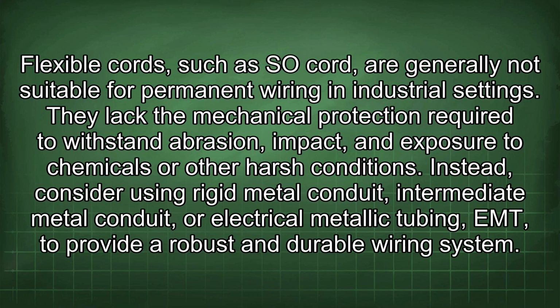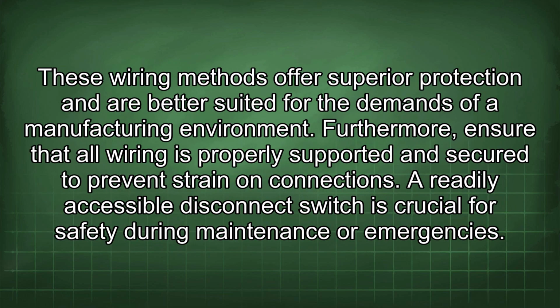Flexible cords, such as SO cord, are generally not suitable for permanent wiring in industrial settings. They lack the mechanical protection required to withstand abrasion, impact, and exposure to chemicals, or other harsh conditions. Instead, consider using rigid metal conduit, intermediate metal conduit, or electrical metallic tubing to provide a robust and durable wiring system. These wiring methods offer superior protection and are better suited for the demands of a manufacturing environment. Furthermore, ensure that all wiring is properly supported and secured to prevent strain on connections.